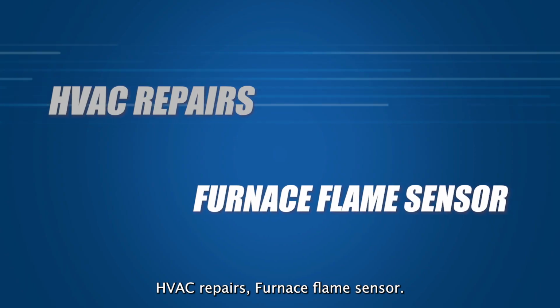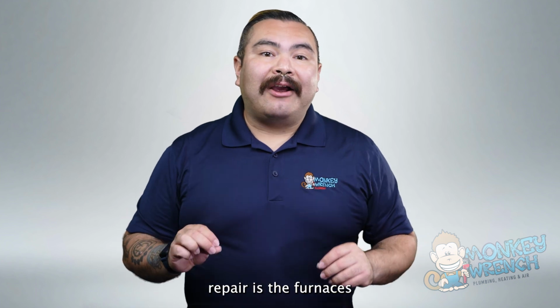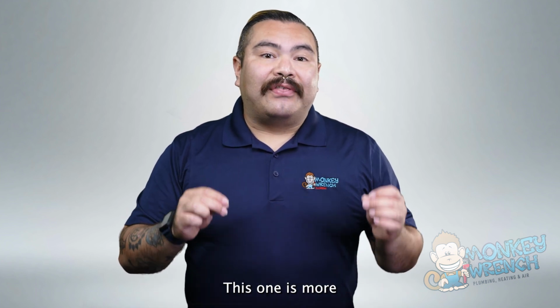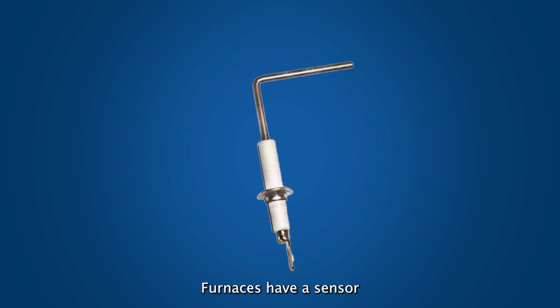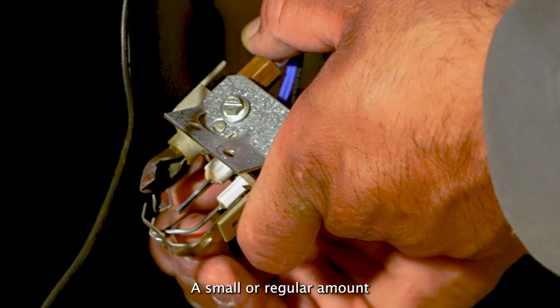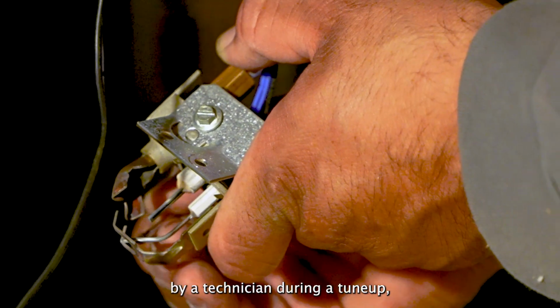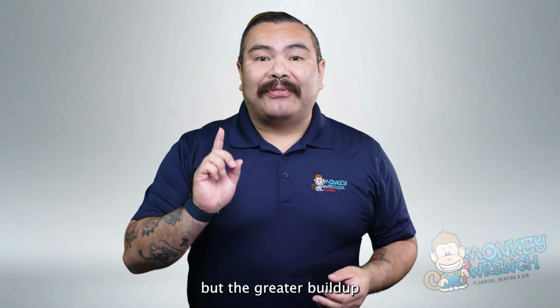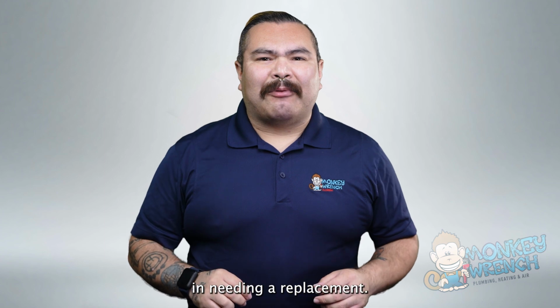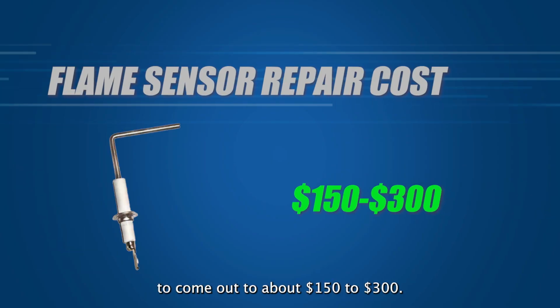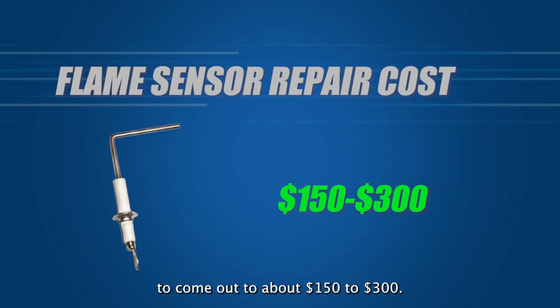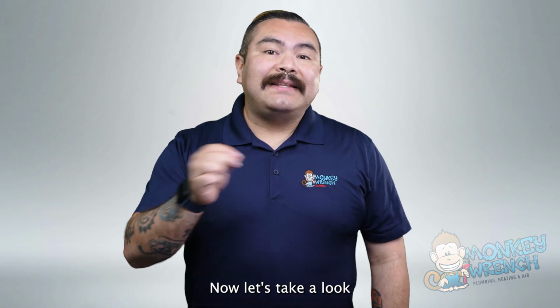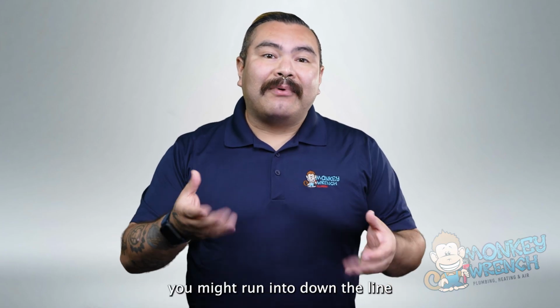Furnace flame sensor. Now, another common repair is the furnace's flame sensor. This one is more or less what it sounds like. Furnaces have a sensor that detects whether a flame is present in the furnace. The main issue flame sensors run into is having an excess buildup of carbon. A small or regular amount can be cleaned away by a technician during a tune-up, but the greater buildup will result in needing a replacement. You can expect the repair to come out to about $150 to $300. Now, let's take a look at some other types of repair costs you might run into down the line.